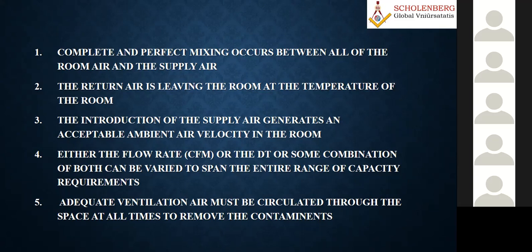Even if somebody wants to measure the temperature, it clearly says not in one place. You have to measure in 4 corners, and then take one in the center, and then take the average of these readings. If I want, for any technician, I always tell them, in, let us say, a 15 feet by 20 feet room, measure the temperature. The ASHRAE standard says you have to measure at 4 corners and in the center and then take the mean. In the 4 corners there will be slight differences.